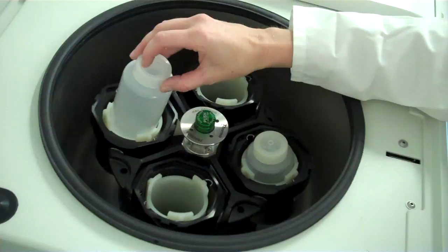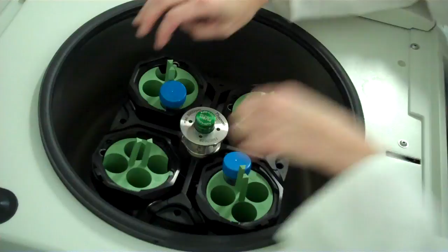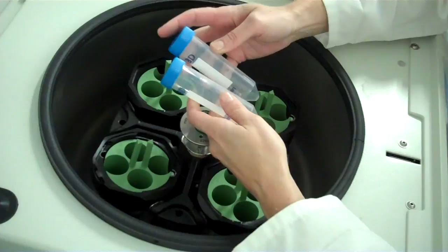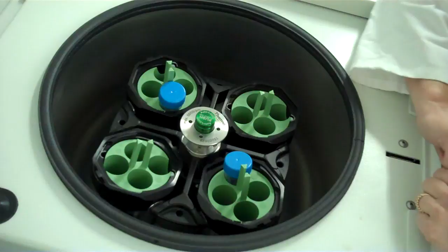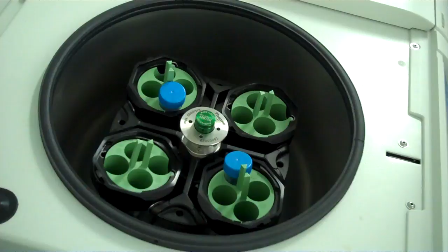This same rotor can be fitted with a different kind of adapter. This adapter fits 50 milliliter conical tubes. And so when you place tubes in these, again, you want them to be opposite each other. These conical tubes must be balanced against each other. And then those balanced tubes are placed opposite each other in the same position in the rotor. So this is how you would centrifuge 50 milliliter conical tubes.